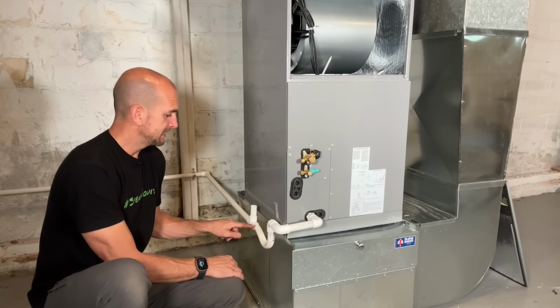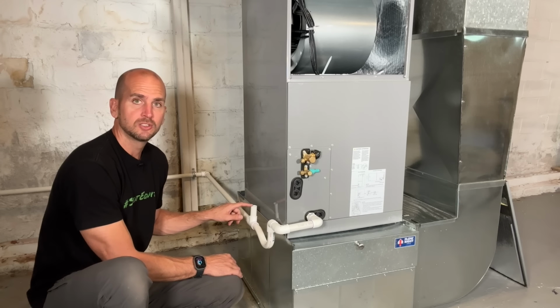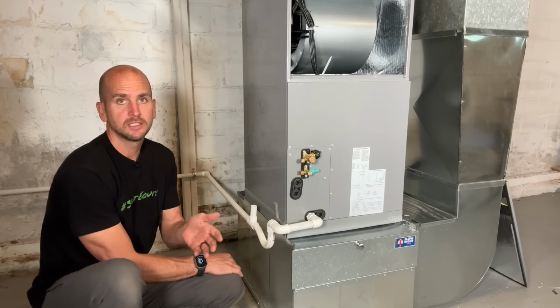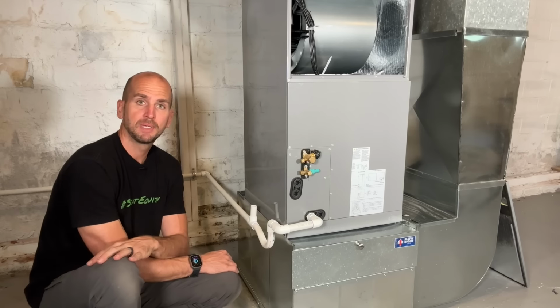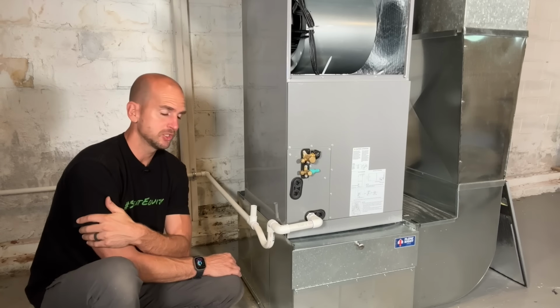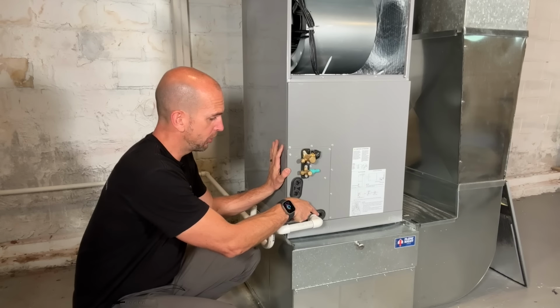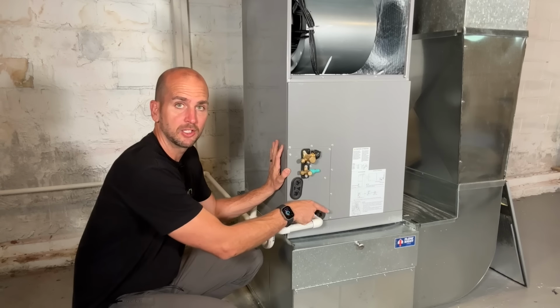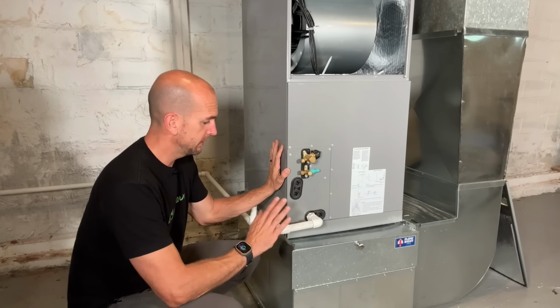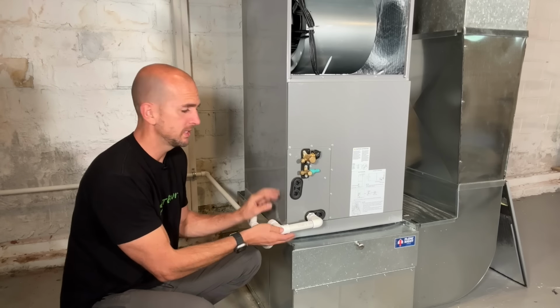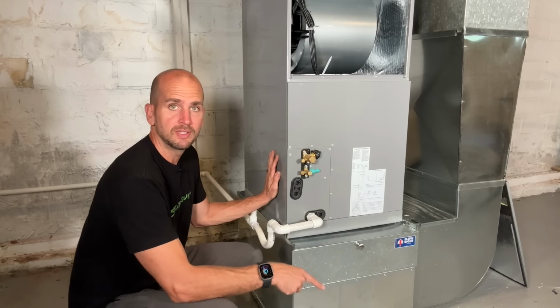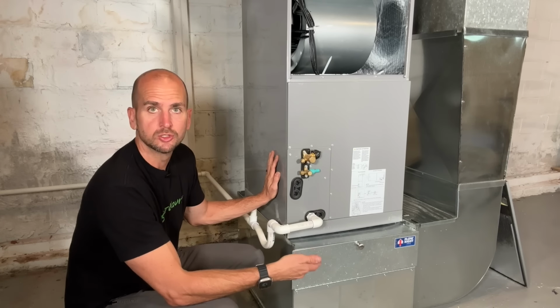I also have a downstream vent here to make sure that the whole drain line can easily drain out to that sump pit where we are discharging the condensation. And then whatever meets your needs for the overflow, I recommend having that going to a visible area. So if there is an issue with your main drain line, you can see the water leaking out of your overflow, and then you can address that issue.